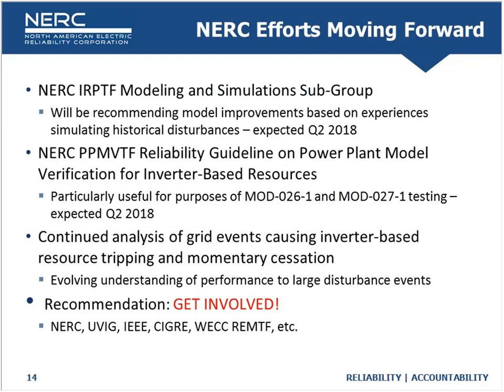The NERC IRPTF — Inverter-Based Resource Performance Task Force — has a modeling simulation subgroup with experts from manufacturers, simulation experts, transmission planners, and planning coordinators, particularly in the Western Interconnection. We'll be providing guidance in Q2 2018. We also have another group looking at model verification and small disturbance aspects, providing guidance on MOD-26 and MOD-27, also coming in Q2 2018. We've had a number of grid events and NERC reports looking at normally cleared 500 kV faults where thousands of megawatts of solar plants are tripping off, which is teaching us a great deal every single day.